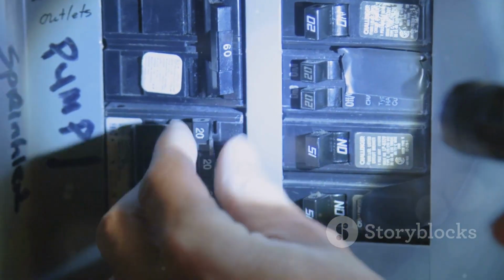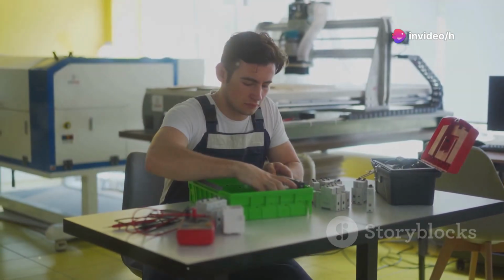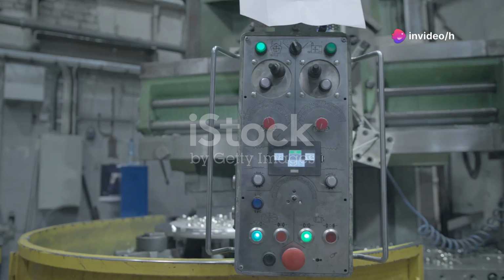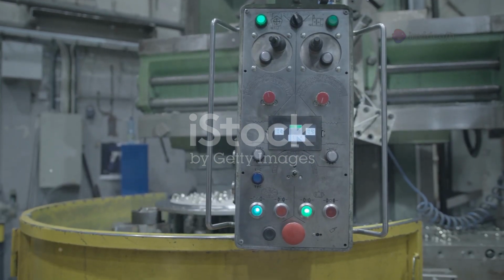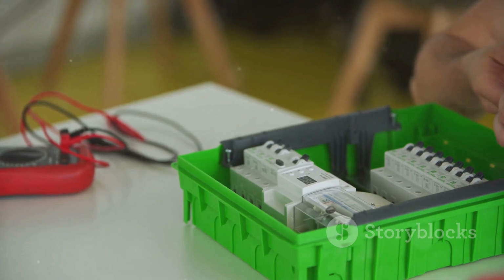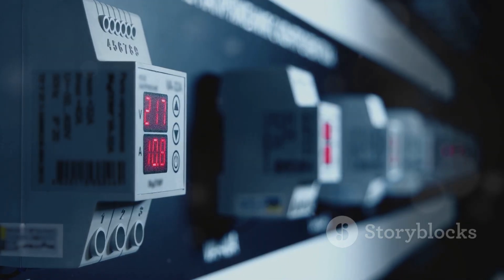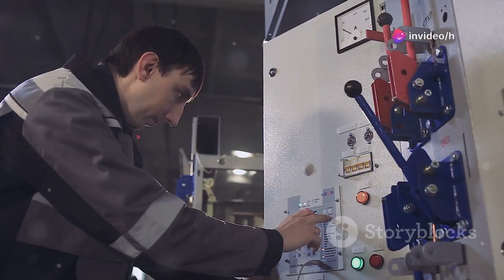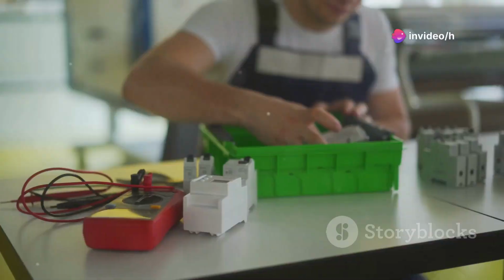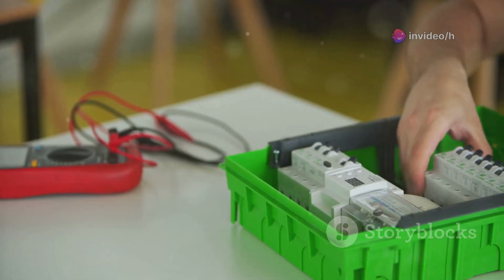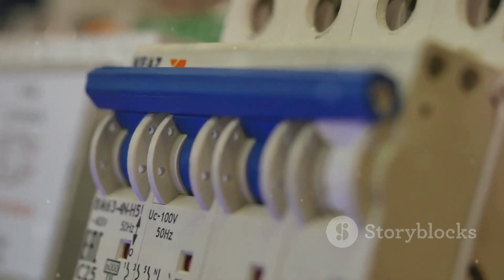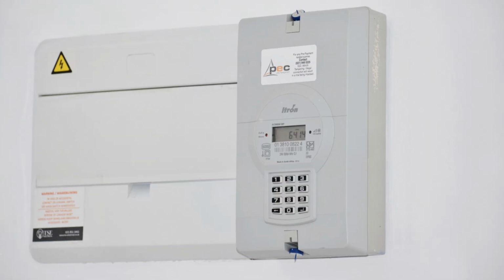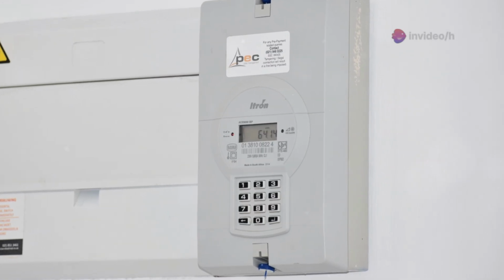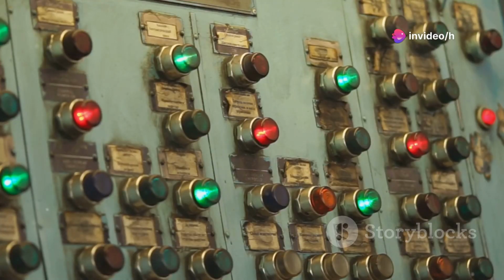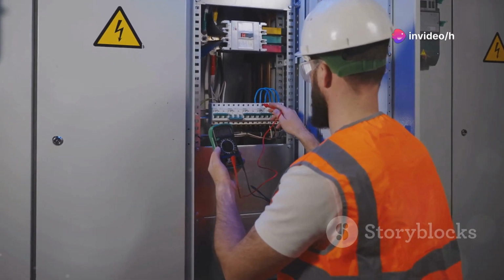Next, let's add a warning system. Stay alert. An alarm system gives instant notice when grid power fails, crucial in noisy or automated environments. Use a buzzer or light powered by a backup battery or UPS. A relay, energized by city power, keeps the alarm off. When power fails, the relay triggers the alarm. Mount the relay and alarm on the DIN rail. Connect the relay coil to city power and the alarm through the relay's normally closed contacts. This setup ensures the alarm only sounds during a true outage. Quick, clear alerts mean faster, safer responses. Small details like this make a big difference.